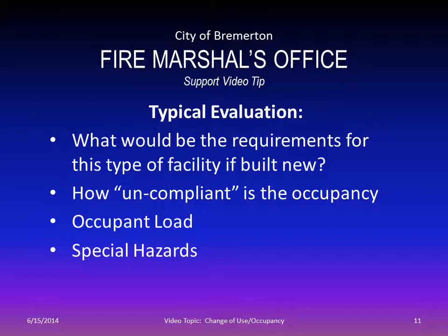What was the building before? If it was a wood shop before and it's going to be a wood shop again, they're not changing any way that they're using it. There's no more people going into it. The fire load's not increased. If it's basically like for like, then it continues as is. However, if we're also doing that and there's a big remodel, then the existing building code kicks in, and we may have some code upgrades at that point. We will also take a look at the occupant load and special hazards. For instance, if it was a wood shop, but now all of a sudden we're going to put in a spray operation that it didn't have before, there's going to need to be some alterations made and some improvements included into the project.